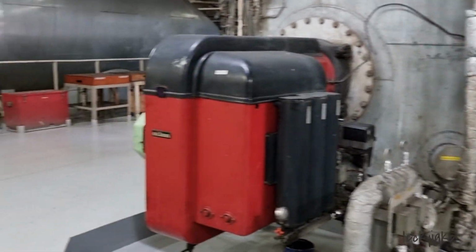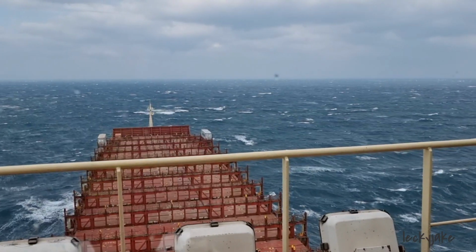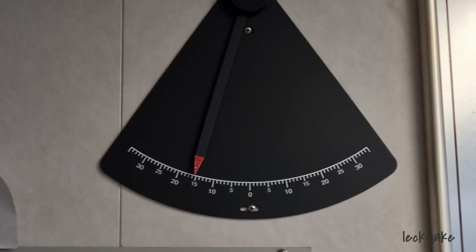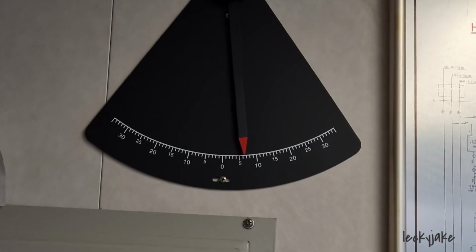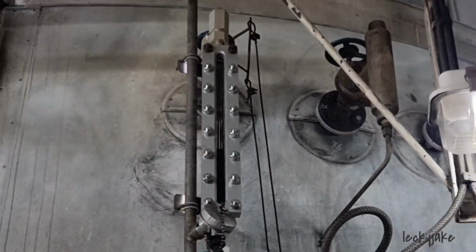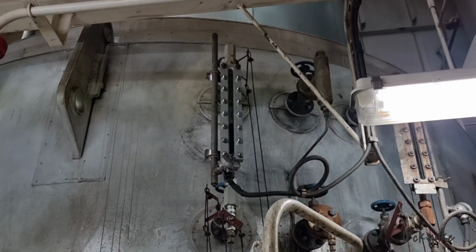So let's say for the auxiliary boiler. For the auxiliary boiler you have the drum. The vessel tends to sail in rough seas. Once the vessel rolls, the level of water will also be dancing inside. Once it shifts to the port side and then to the starboard side, the level of water will also be affected, and then you might have a high level alarm on the drum which will trip the system.